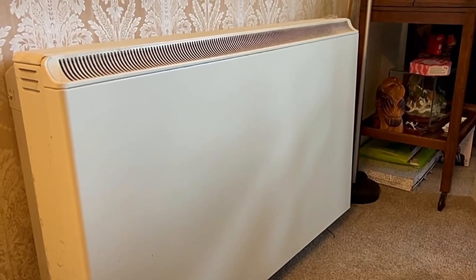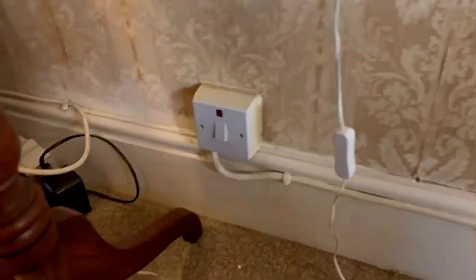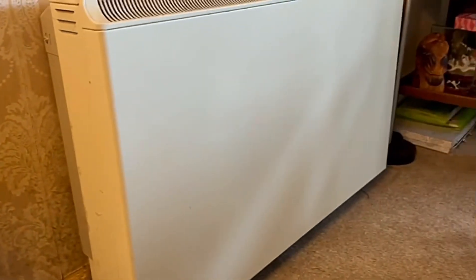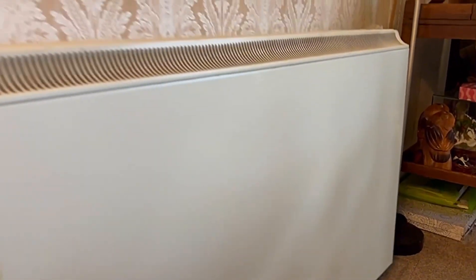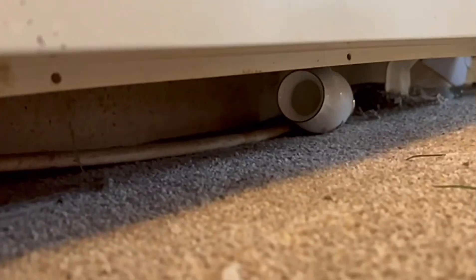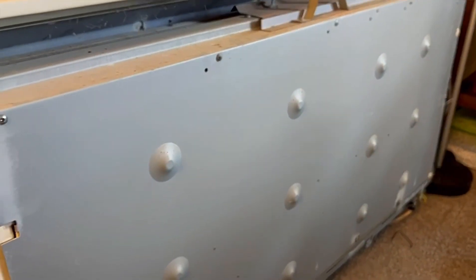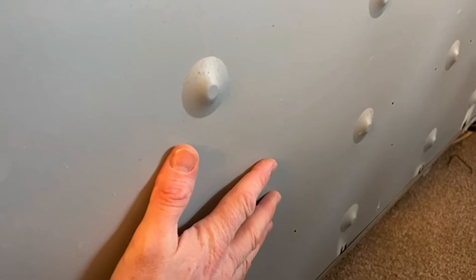I'm out this morning to fix this storage heater - I've already been out here once so I know what the problem is, but I'll go through some things that will hopefully help people in the future. It's isolated and on Economy 7, so it only comes on at night. It's a Creda storage heater. If you look underneath you'll see two little screws - undo those and the front cover just lifts off, and you're faced with this panel.